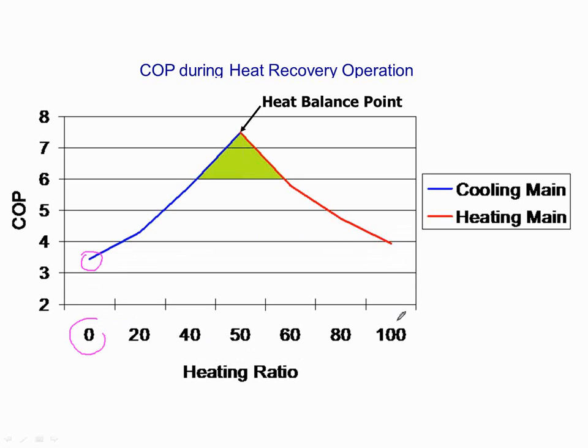On the opposite side, at the 100% ratio, I'm all in the heating mode. Nobody wants cooling, everybody wants heating. Those are my 2 least efficient points. Anything in between, where some zones want heating and some want cooling, my efficiency is going to improve. My COP is going to get better. It's going to go from 3.5 or 4, depending on what mode I was in, up to 6, 7, something like that.